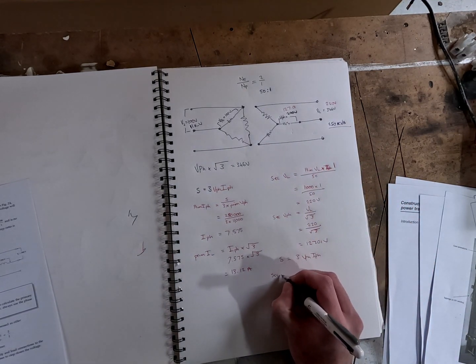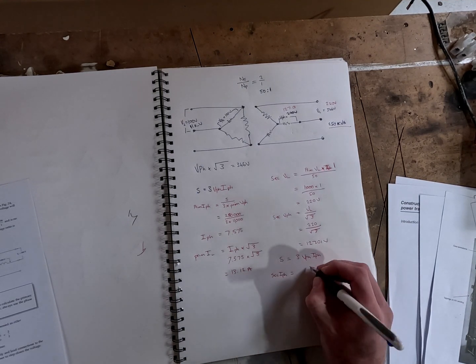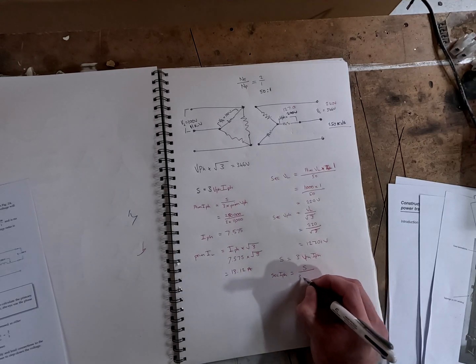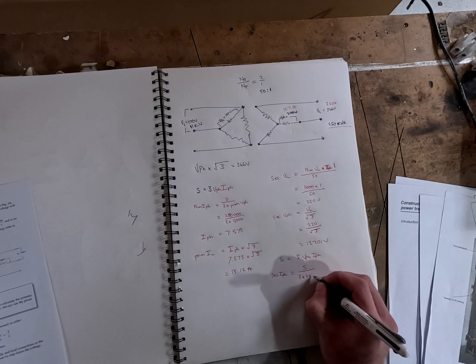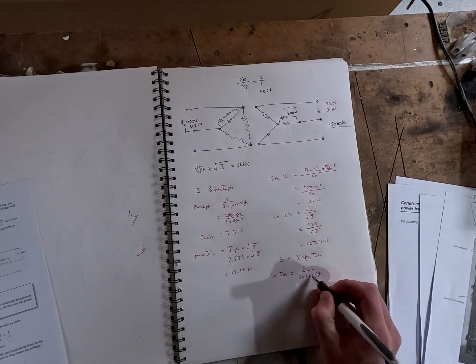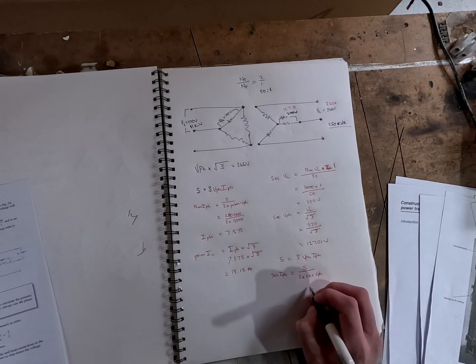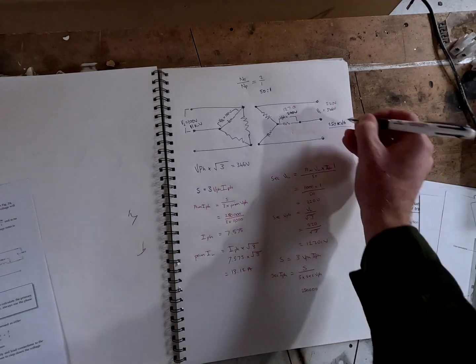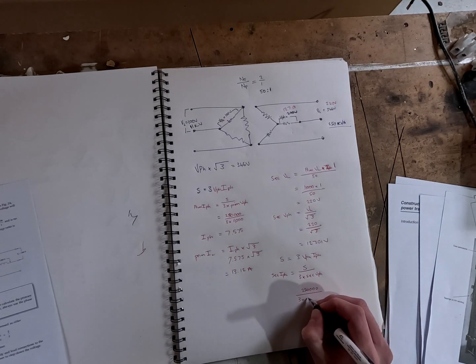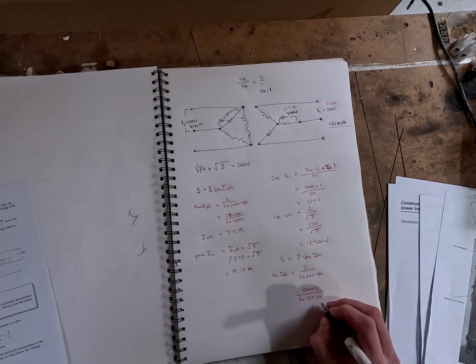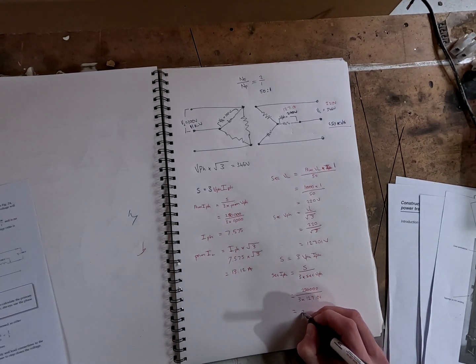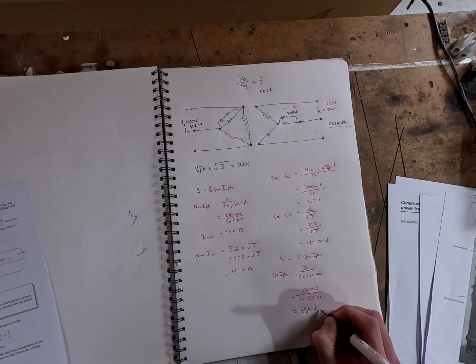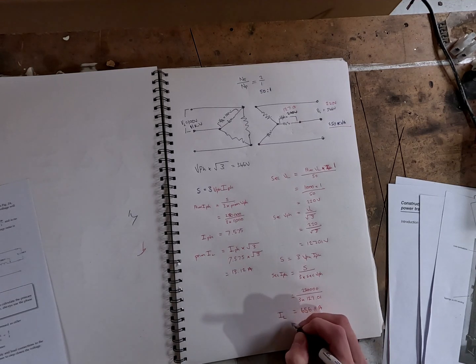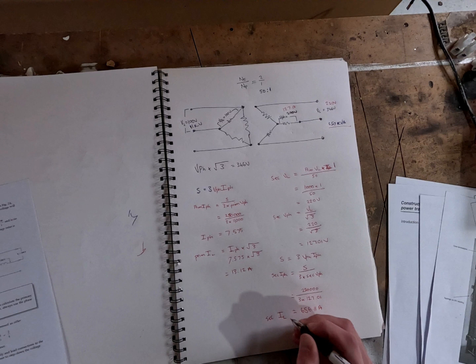The secondary phase current equals S over 3 times the secondary phase voltage, because we are on the secondary side, so that's 250,000, because that's the kVA of the transformer, divided by 3 times 127.1, which equals 656.1 amps is our line current on the secondary. So just like in a delta wiring, how the phase voltage and line voltage are the same, when you have a star, the line current and the phase current are equal.